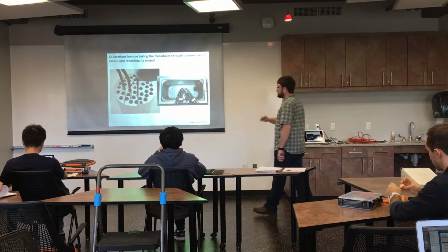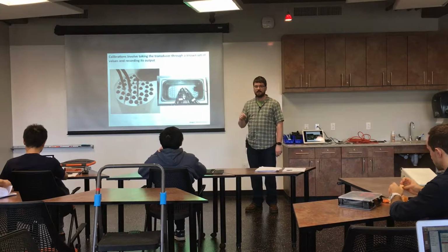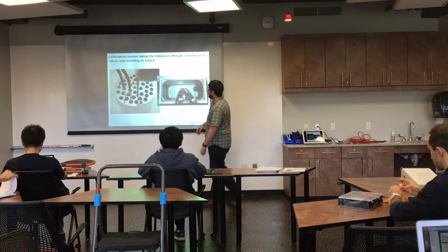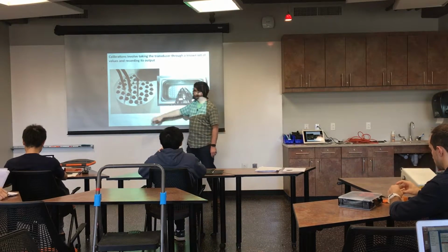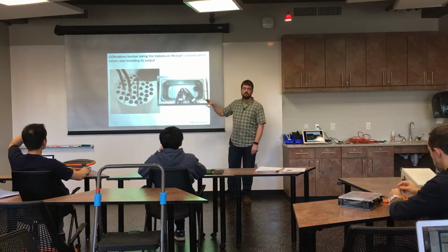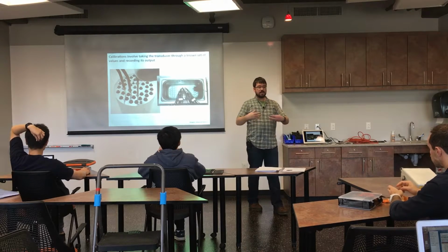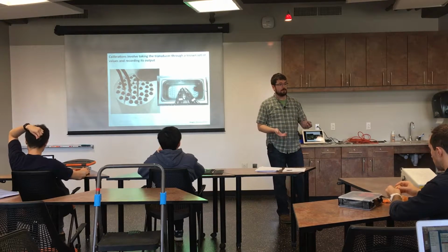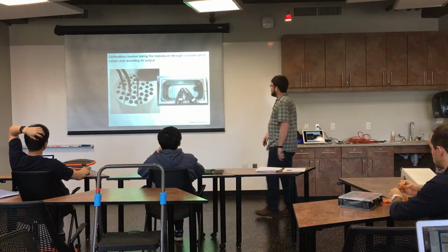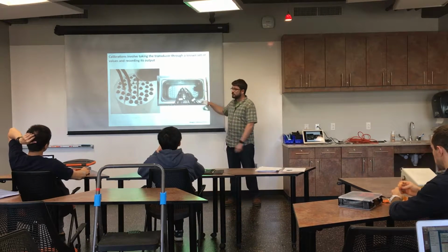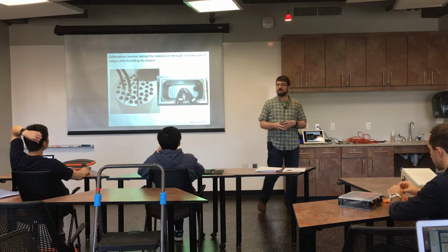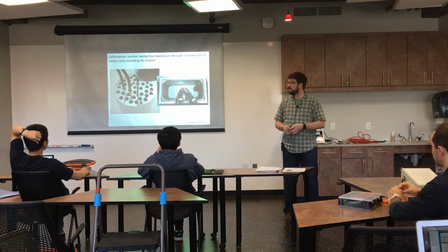So what we do is we take the transducers through a known series of values, a series of values that we can trace to real physical units. For example, if we were calibrating a bunch of temperature sensors, we could stick them all together in this piece of metal and put it in a water bath that is precisely controlled. We could mix ice in, and we know by definition we have water and ice coexisting. That's 0 degrees Celsius. Or we could boil it. We could set this, if it's a bath that we could change the temperature on, but it also has to be somehow calibrated. The idea is you have to have something that you can trust, something that is a standard.